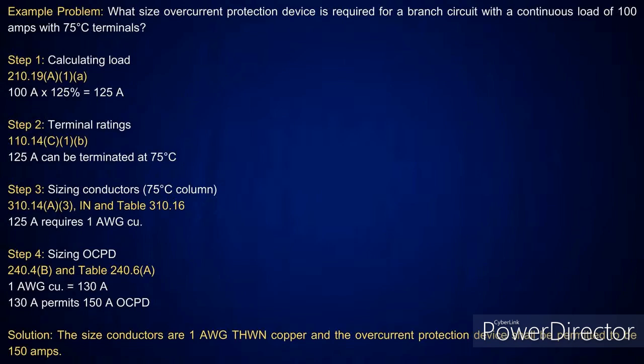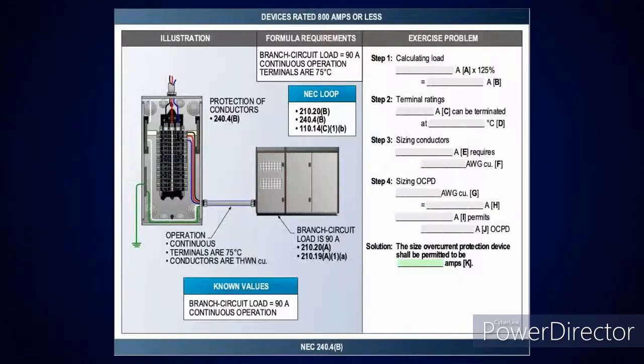And it's probably hard to protect the load if it's unknown. Yeah, that's what I'm saying. I know what you're talking about. But when you start looking at these things, these are things you have to consider based on the conductor, and that's why 240.4(B) is written that way. And if you remember when we started all this, I went over all the terminals and everything and explained that. There's a reason I did that, because I wanted you to be aware of how those terminals apply when we got to this point where we were going to size the overcurrent protection devices. Basically, I've done everything in a step-by-step format to get you up to this point. I just didn't cram it all in your mind at one time. Okay? So, I just use adjustable overcurrent devices on everything, so it's all good.